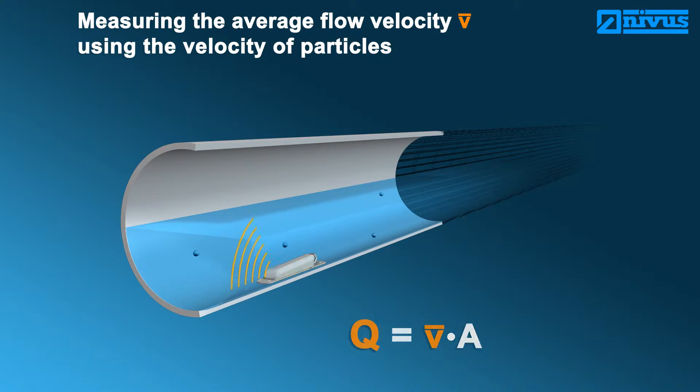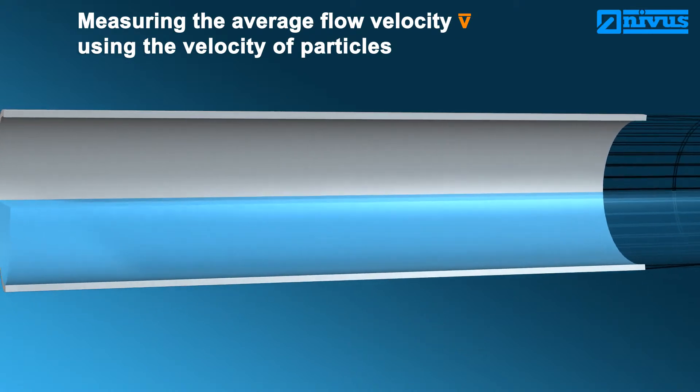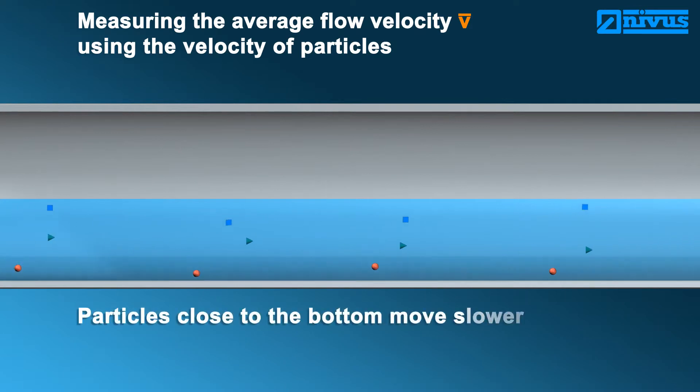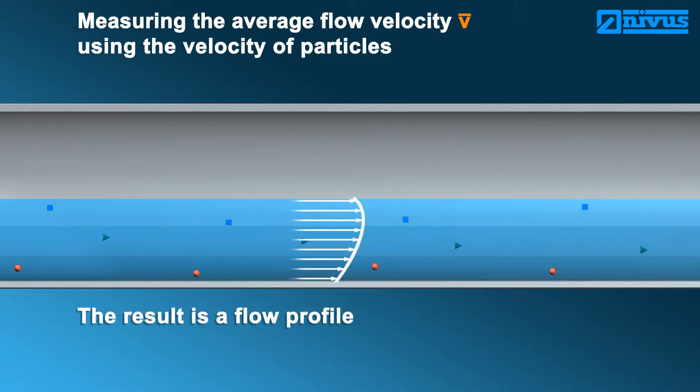The main difficulty while detecting the average flow velocity is that there are varying velocities prevailing at varying levels. The medium and hence the particles normally flow slower at low levels than at higher levels. From this, a so-called flow profile can be obtained.